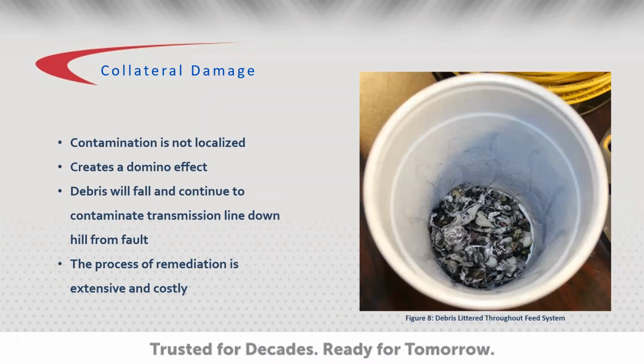And then this final image is to show basically the trickle-down effect that happens from a serious fault. The collection of Teflon, brass, and copper debris was gathered from various Teflon pieces at different flanges along the vertical section. This debris is so fine that it can travel through the tuning holes located in the Teflon insulators. An isolated fault can incur widespread damage and extensive downtime, as it would take many weeks to comb through each section.